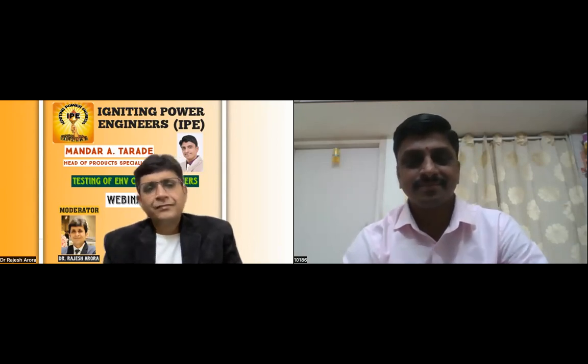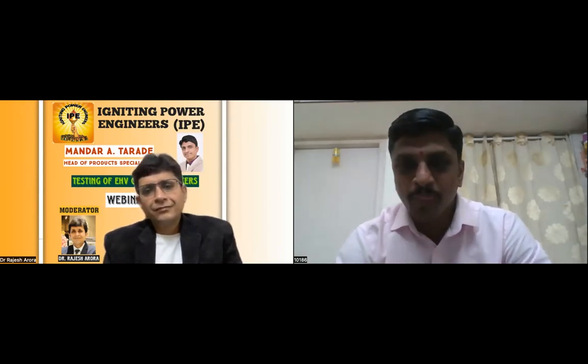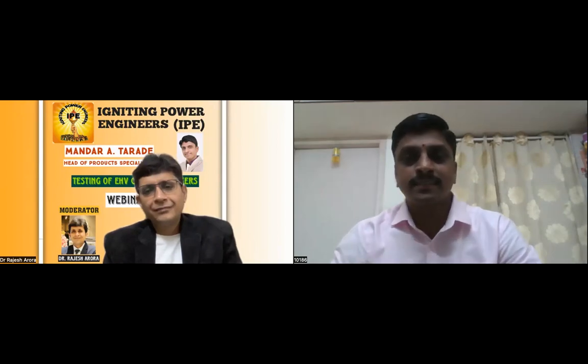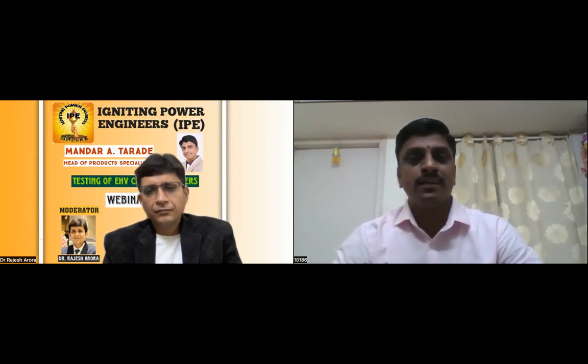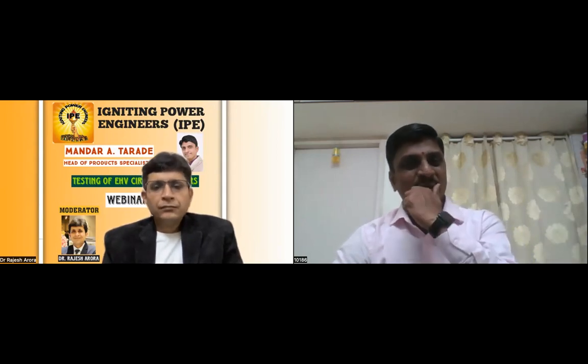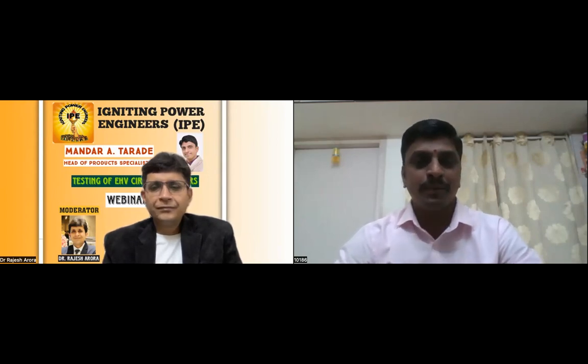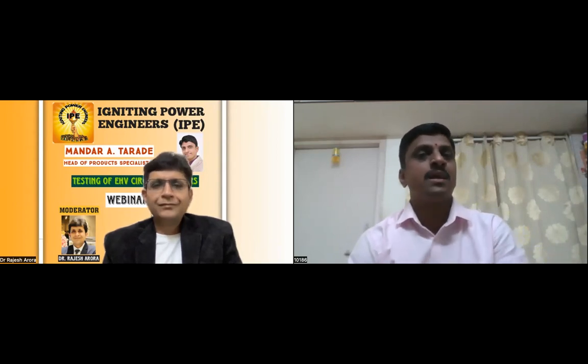My last question is, what is the effect of PIR? PIR is basically the pre-insertion resistance, which comes into the picture 8 to 10 milliseconds prior to your main contact. It is simply to control the inrush current passing through the line. Normally many failures occur because of the PIR. Whenever your line length is more than 80 to 100 kilometers, PIR comes into the picture. The significance of the PIR, the pre-insertion resistance, is to control the inrush current. That is the thing, sir.